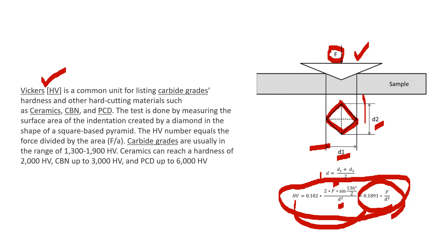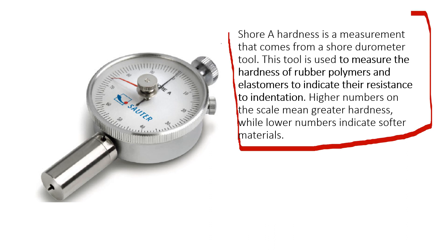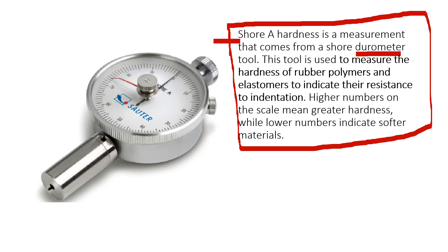For Shore hardness we use a durometer, which is used for rubber. If you work in industrial sectors you may see expansion bellows, which are rubber components. To check the hardness of expansion bellows we use a durometer. Shore A hardness is the measurement from the Shore durometer tool, used to measure the hardness of rubber, polymers, and elastomers — indicating resistance to indentation. A higher number means greater hardness, but higher hardness also means more brittleness.